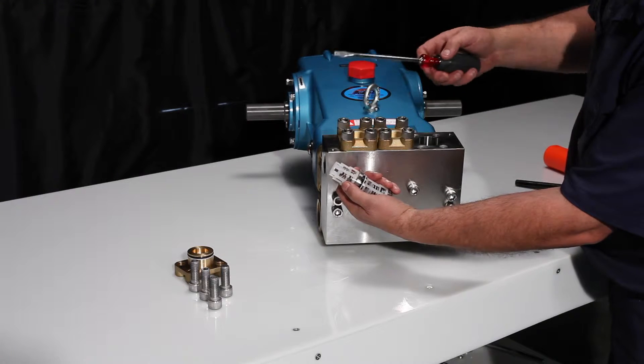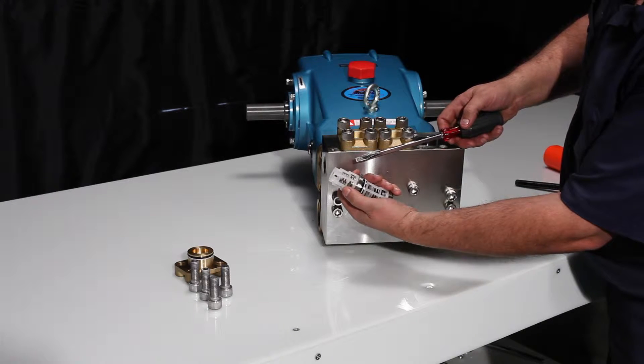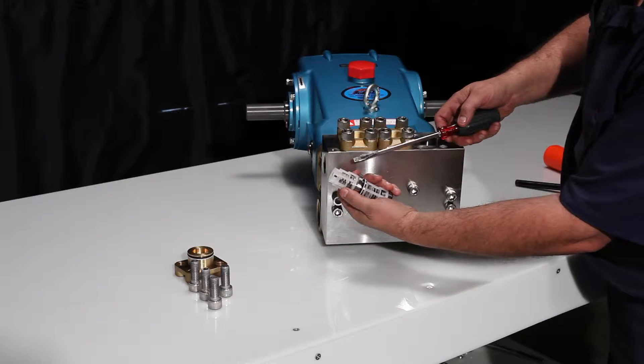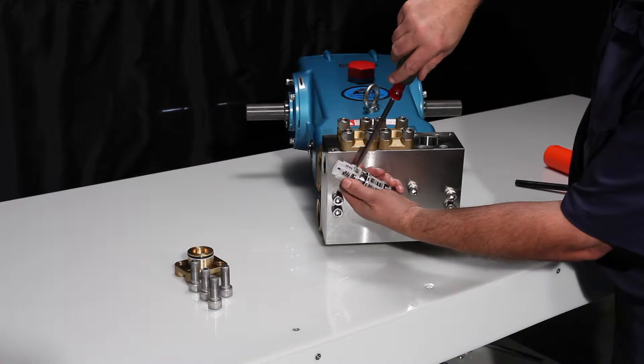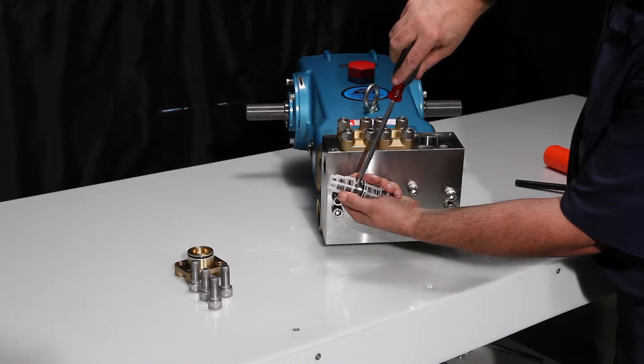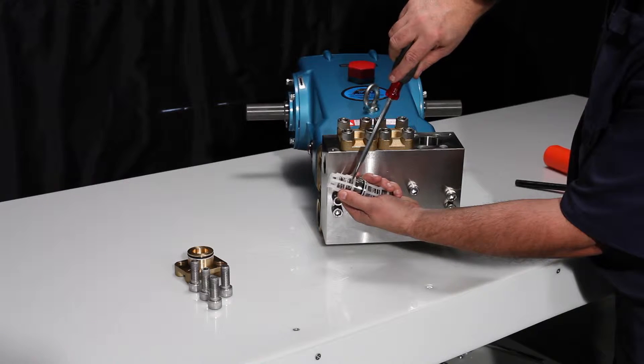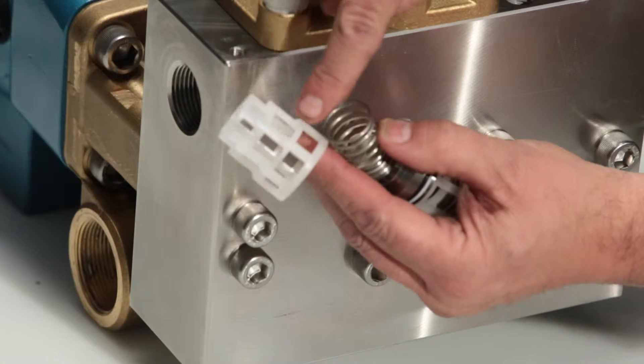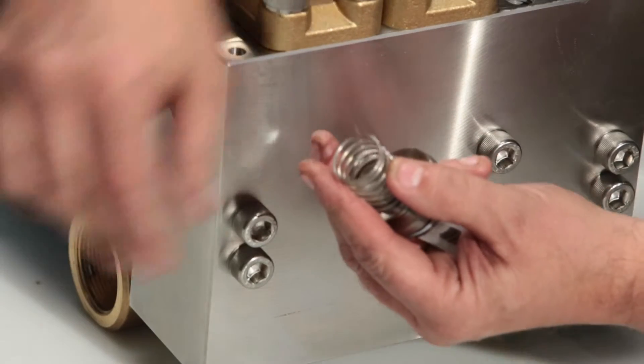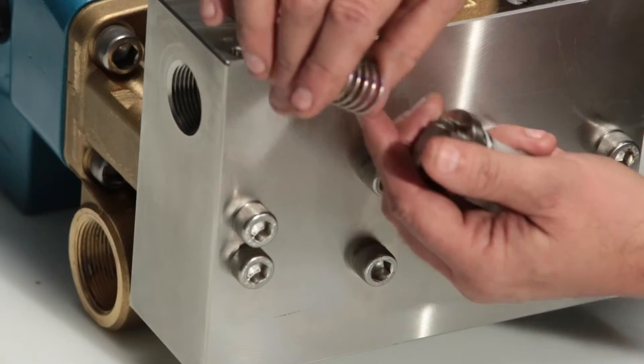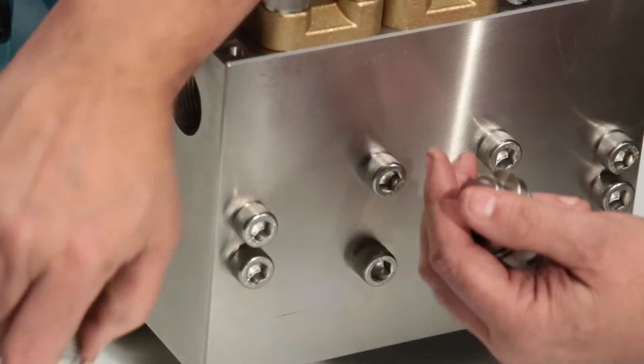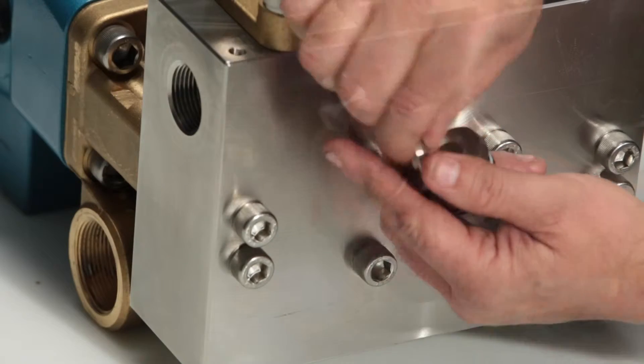To inspect the valves, start by placing a flathead screwdriver between the valve retainer and top of the valve and twist. This will create separation between the retainer and seat, which can then be removed. Inspect the valve retainer for any cracks, the spring for proper tension, and the valve for any pitting.